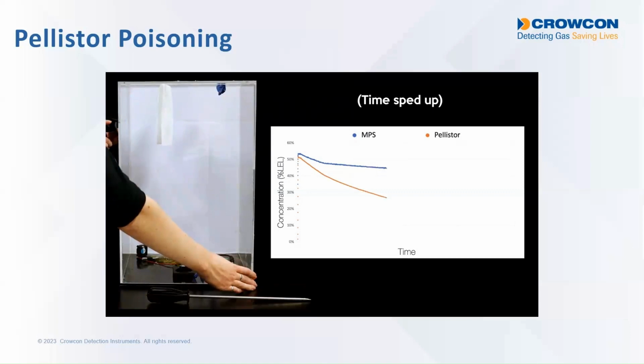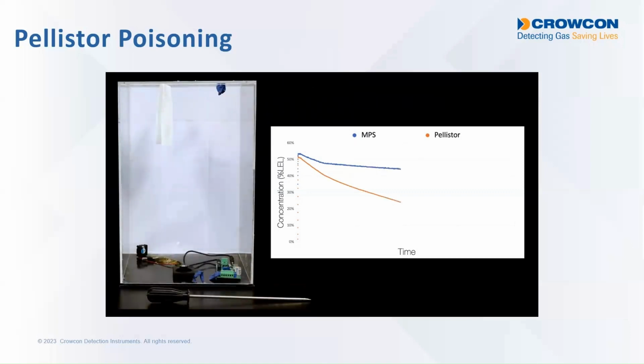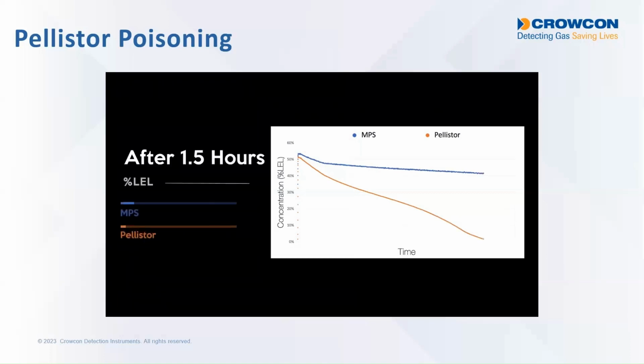So now some of that silicone spray has been squirted onto the towel that's hanging at the top there. There's a fan in the chamber just moving around the gas. And you can see pretty quickly that the red line from the pellistor sensor starts to dive downwards. And that's because the pellistor is being poisoned and becoming less responsive to the gas. So you can see it's becoming less and less responsive.